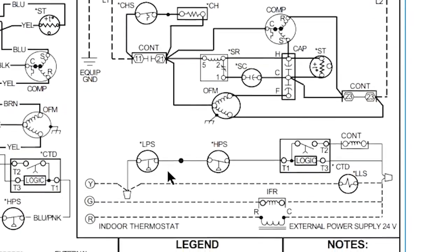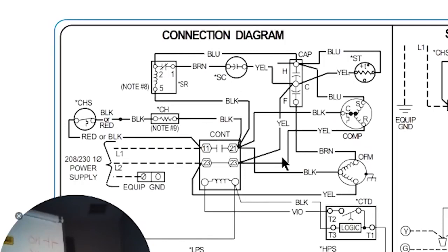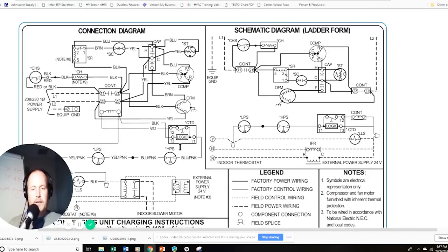The biggest things to know are that every symbol has a meaning, and understanding those meanings helps you understand how the system is operating — you can even catch manufacturer mistakes. The connection diagram shows everything in a position closer to how it appears physically, which is helpful for locating components inside the unit. The schematic diagram is really the way to go for diagnosis and tracing out a circuit. Here's a simple ladder schematic example — everything connected between L1 and L2, tracing across from one side to the other.